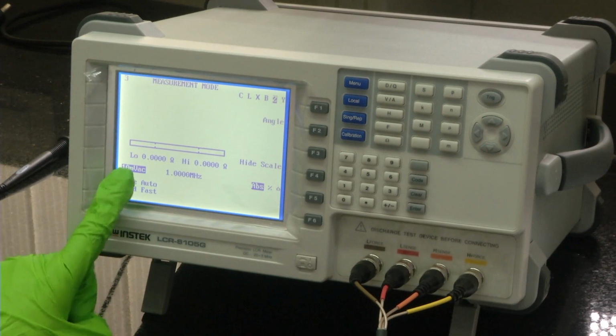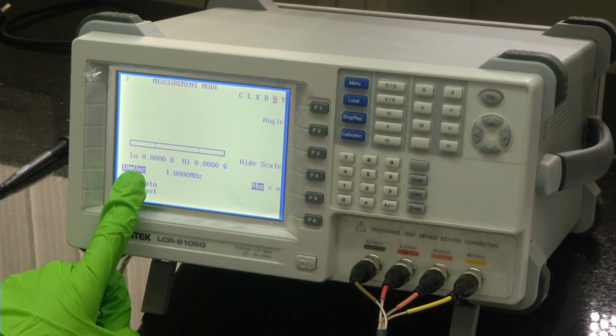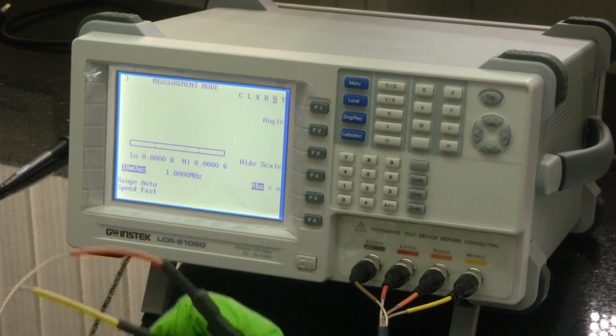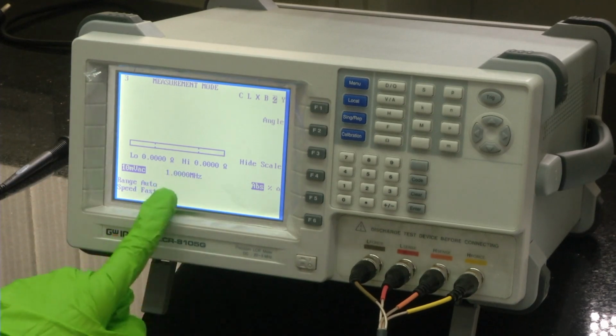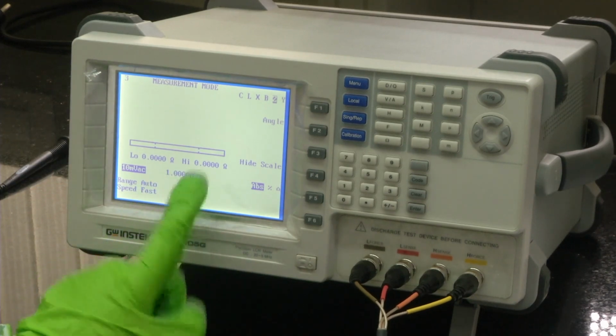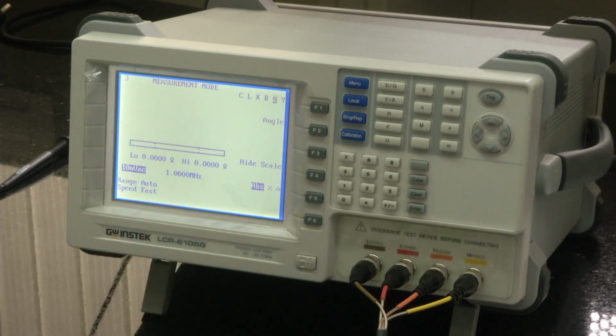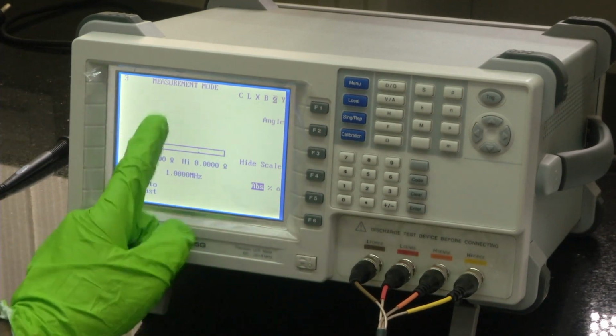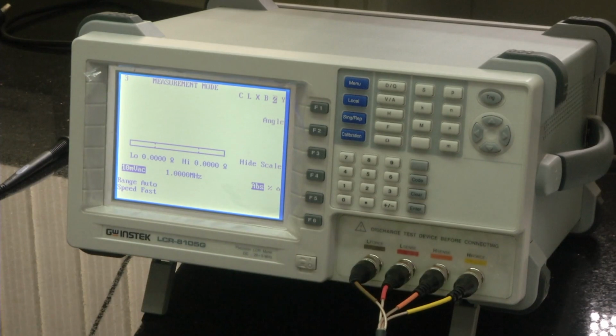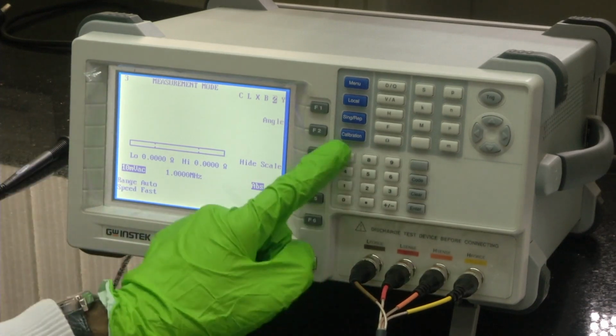So, that is why this 10 millivolt AC what we see here is the force voltage that will be applied from the sensors, and here you see what is the frequency that it will measure at. And once we probe something, that impedance value will come here. Let us not jump to things now. First thing to do before measurement is to do calibration. So, let me press calibration here.